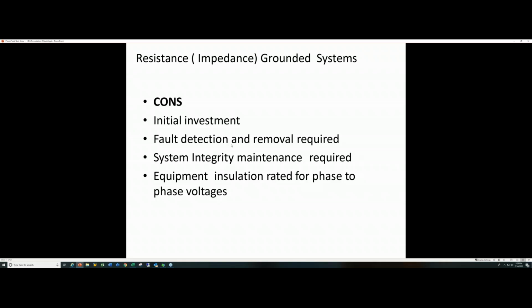System integrity maintenance, that's required. So that's a con. There is some maintenance required on an HRG system. You have to make sure the resistance and the resistor is in sound condition and the unit is on and it's connected and it's serving its purpose. And also equipment insulation. The insulation rated for the phase-to-phase voltages is higher.